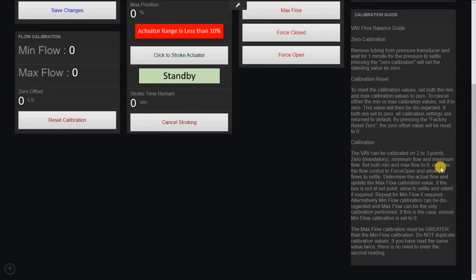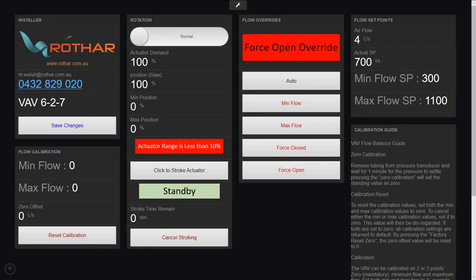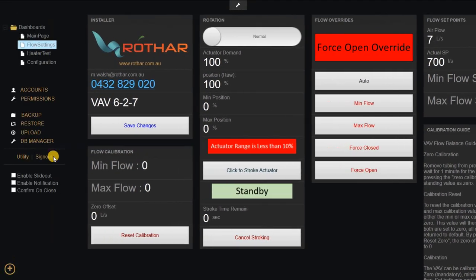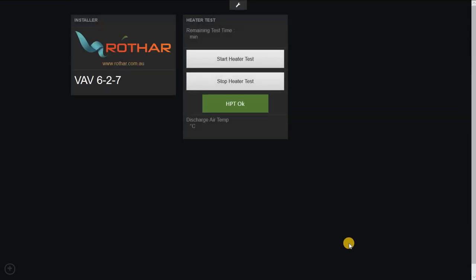We also give a description on how the box behaves and how the box will handle its min flow, what the guys should do to calibrate the box for the best performance. We also allow electronic duct heater test from here. With this, because we have minimum flow safeties inside the VAV, this will override those safeties in the VAV for a 60-minute period. So click on the Start Heater Test.